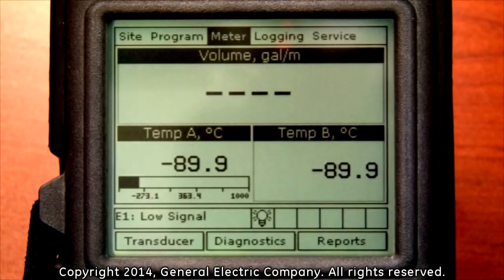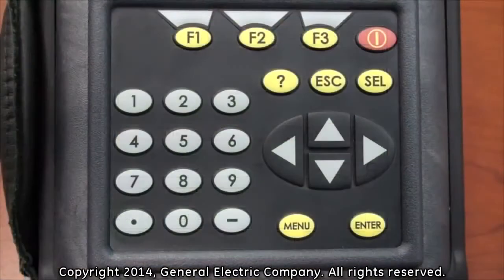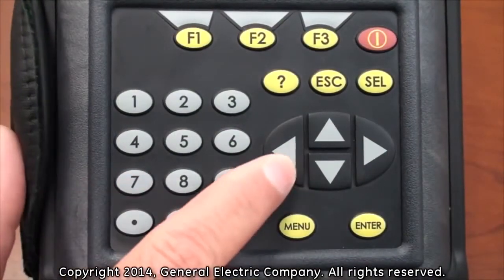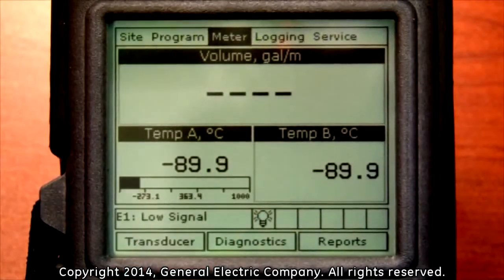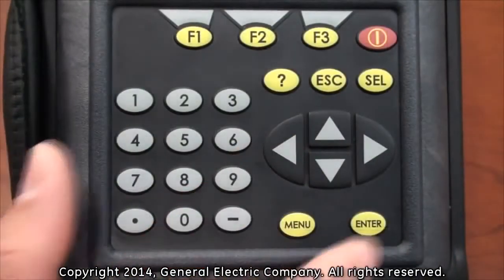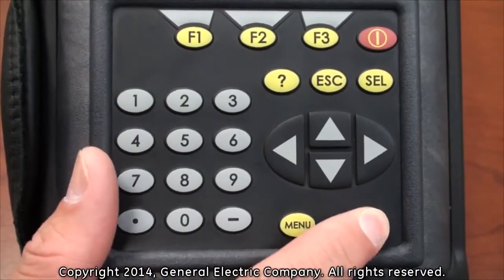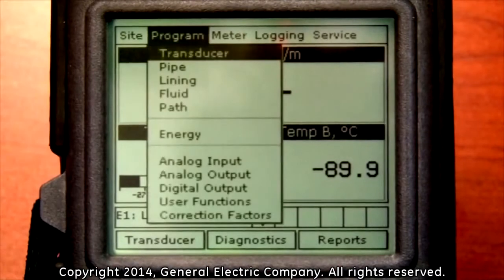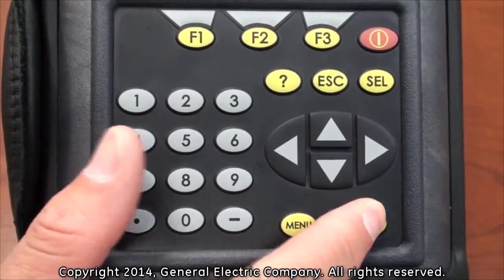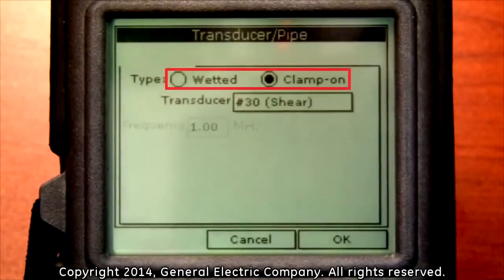Now that the unit specification has been selected, you may proceed to program the PT878 for a clamp-on system. Using the arrow keys on the keypad, scroll over to highlight the Program selection. Press the Enter button with the program selection highlighted. This will bring up a drop-down menu, and the first highlighted selection will be the transducer. Press the Enter button on the keypad. This will bring up the transducer type options.